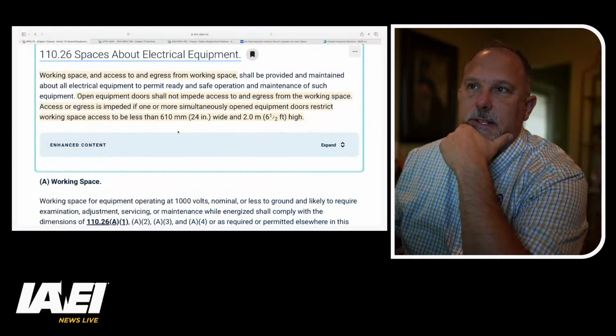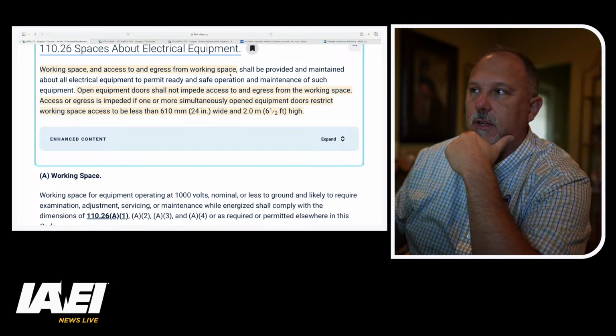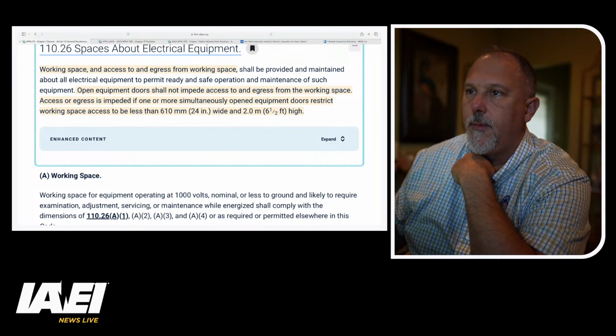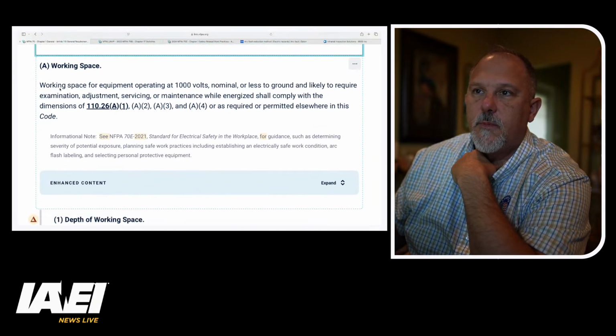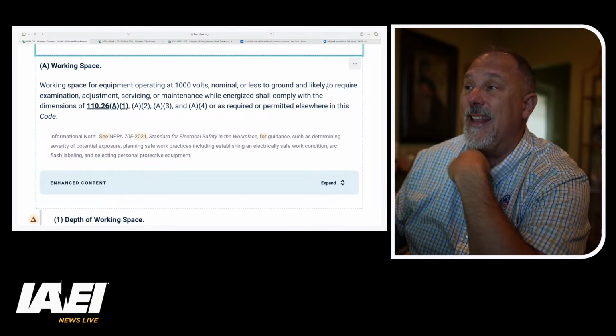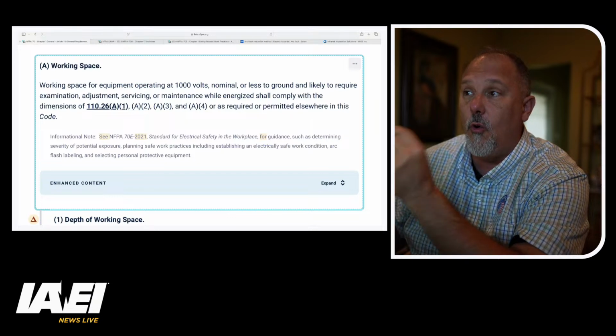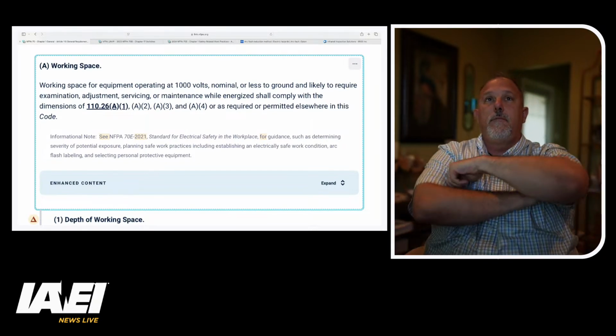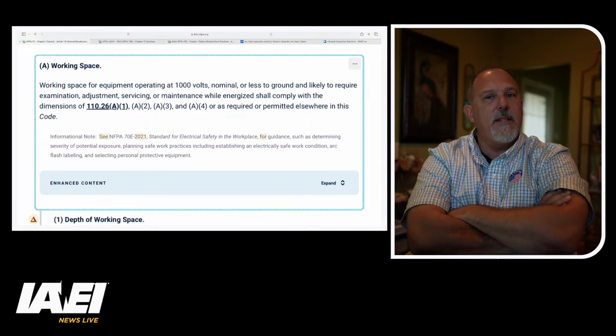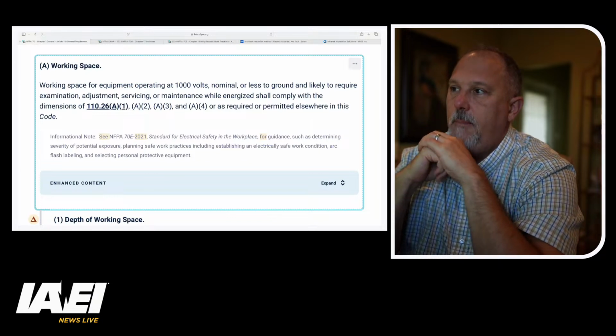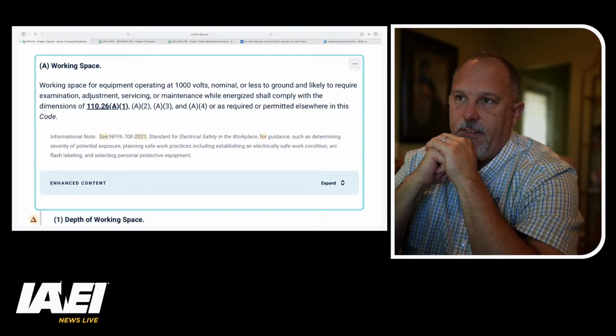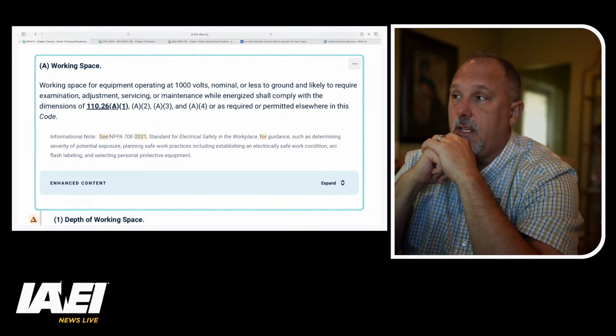Testing for potential. If it's considered energized work, then how the heck do we in 110... I'm looking in 110.26, spaces about electrical equipment. Working space and access to and egress from working space shall be provided and maintained about all electrical equipment, open equipment doors, etc. Working space for equipment operating at 1,000 volts nominal or less to ground and likely to require examination, adjustment, servicing, or maintenance while energized. Maybe it's the while energized, Andrew. Maybe that's the part that gets me out of having working space on a non-fused disconnect.